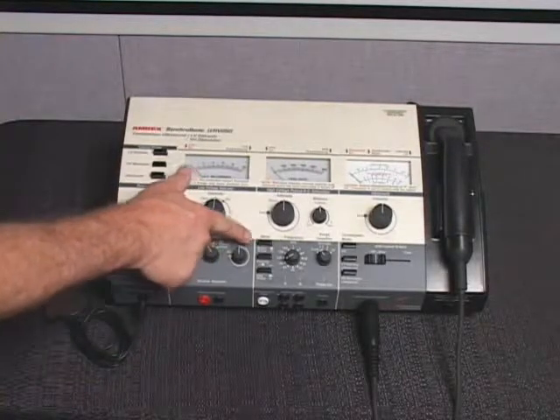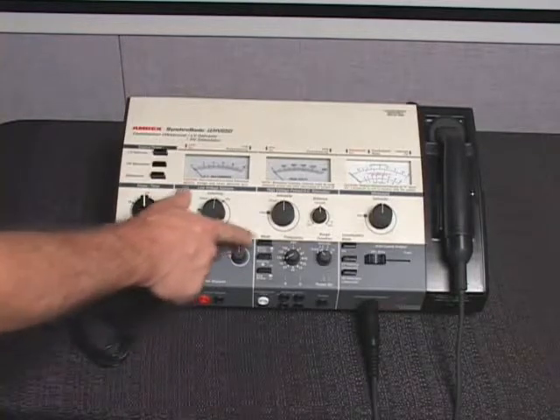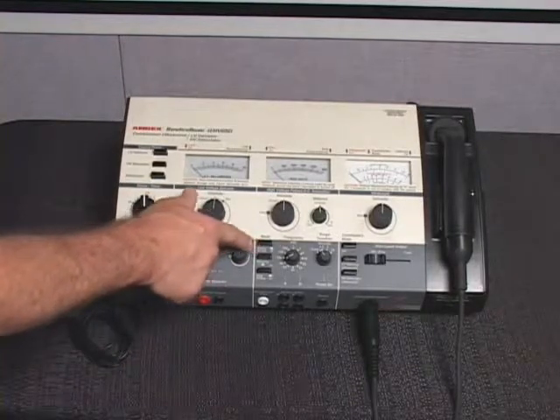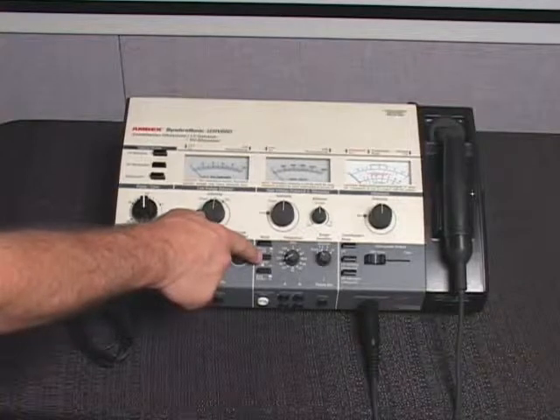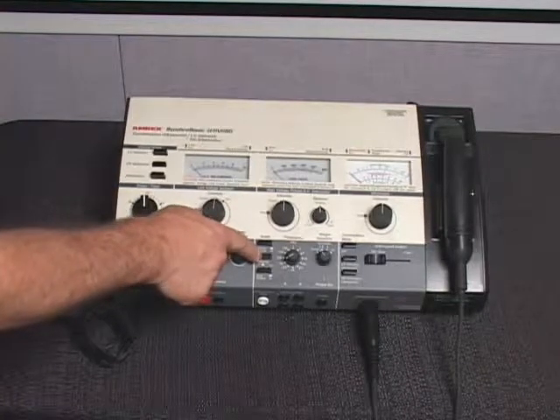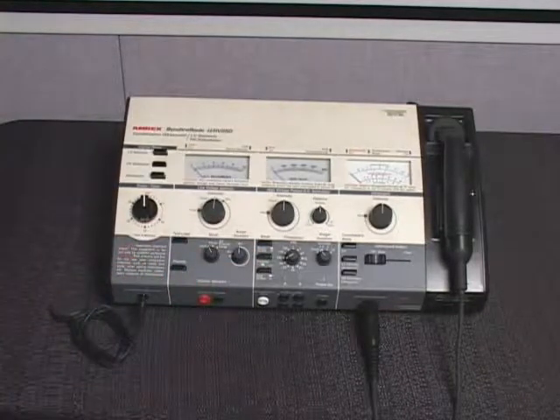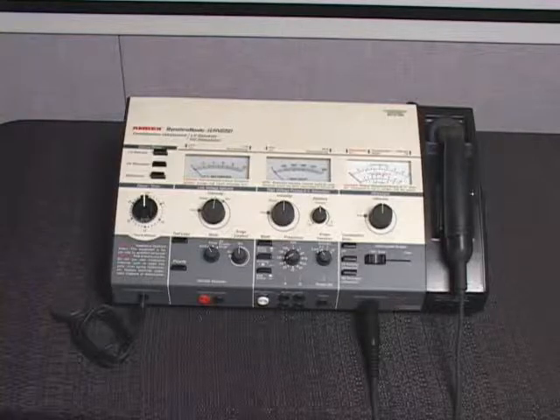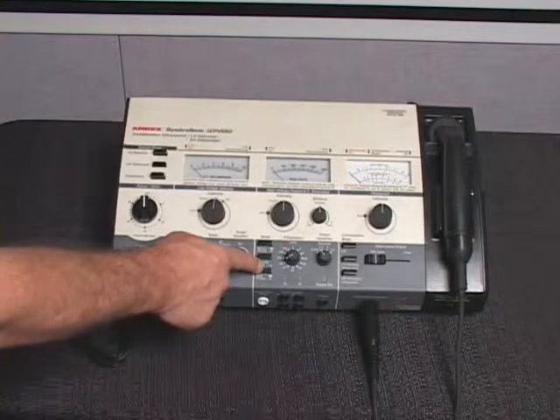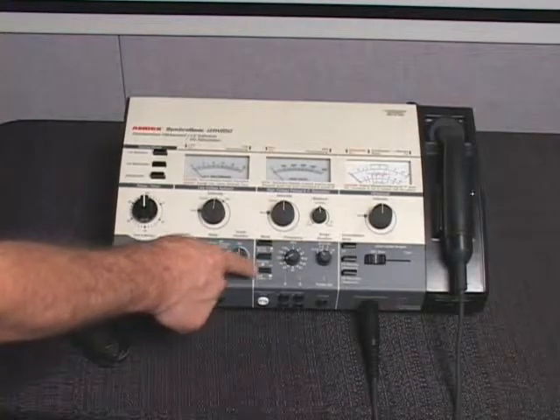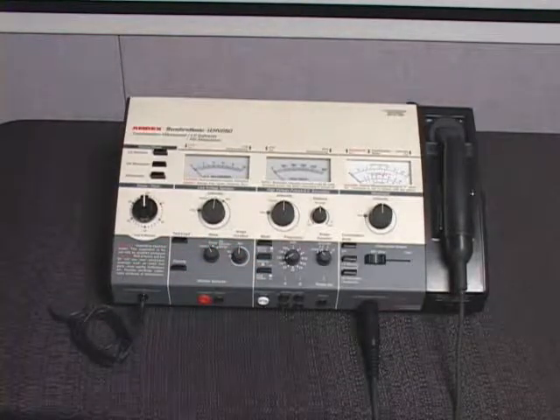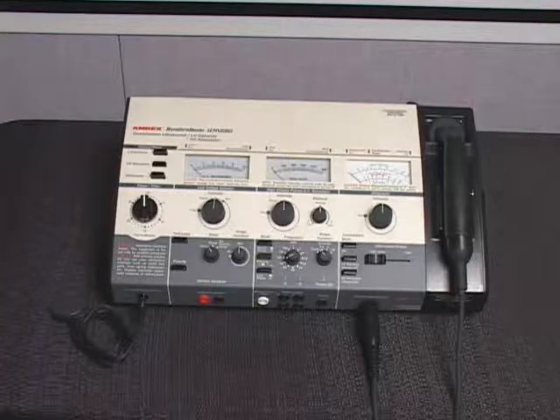Set the mode switches to the desired output modes. The reciprocal surge switch can be set to reciprocal or surge mode. The positive-negative switch can be set to positive or negative polarity for the dispersive pad output jack. The polarity setting may be changed any time during treatment. The pad probe switch can be set to pad or probe mode.